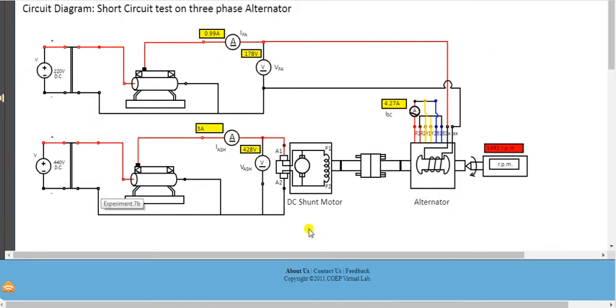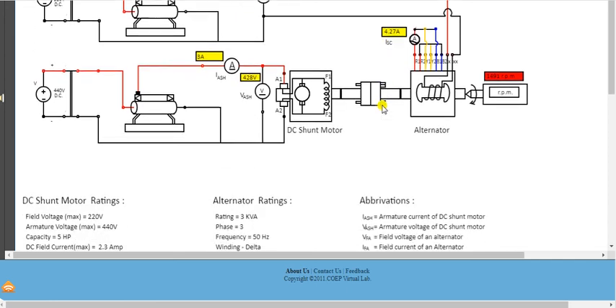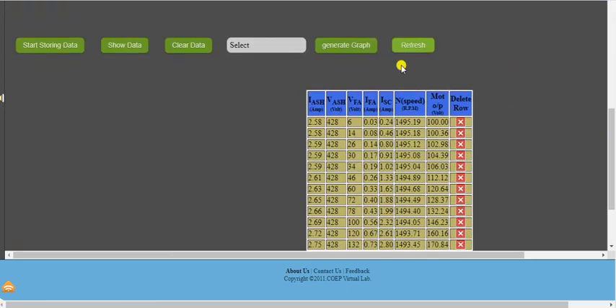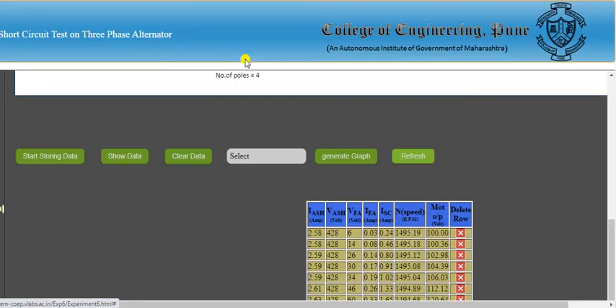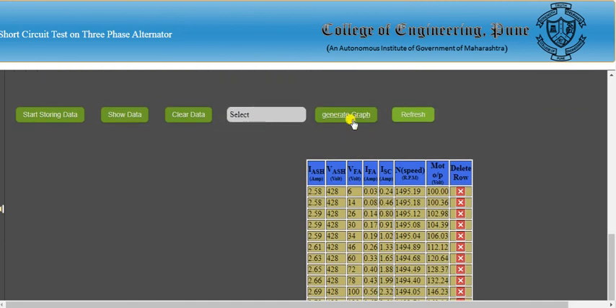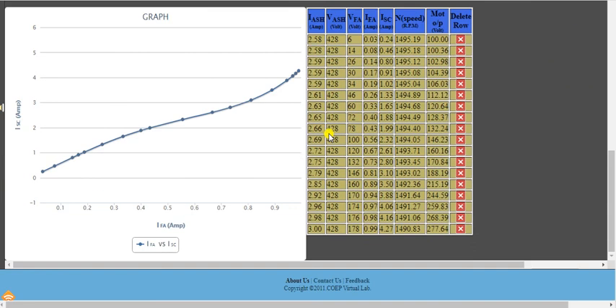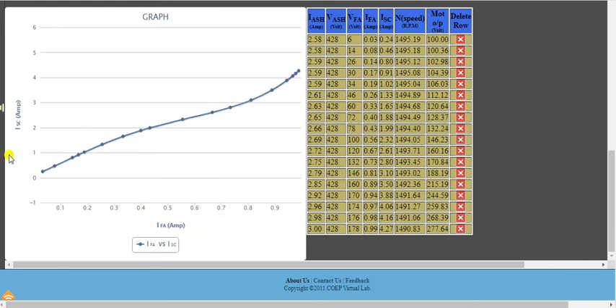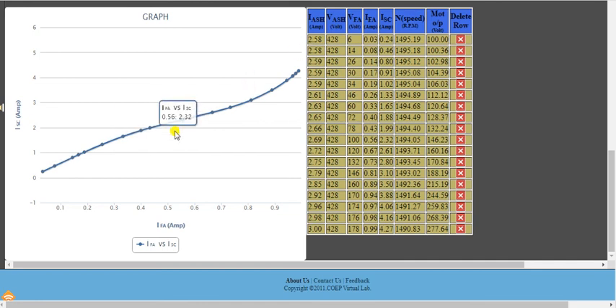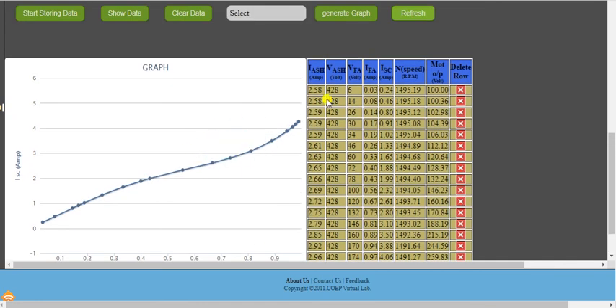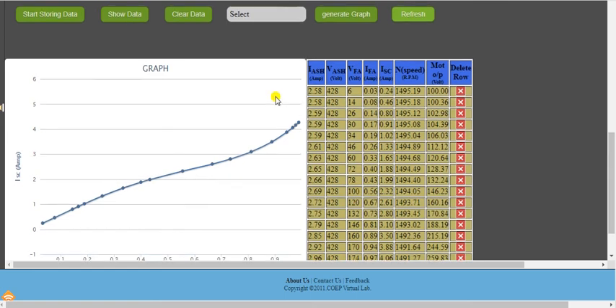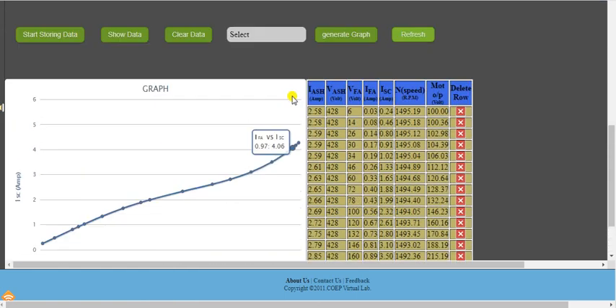Select 'Field Current vs Armature Current' and click Generate. The resulting graph is essentially a straight line — the short circuit characteristic is very close to a straight line, as expected for a synchronous generator under short circuit conditions.